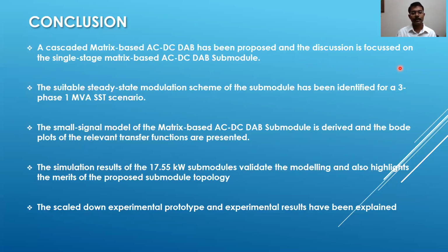And we have also provided the Bode plots of the relevant transfer functions that might be useful for control system design. We have shown the open loop simulation results of the 17.55 kilowatt submodules that validate our proposed modulation scheme, and also it shows the merits of the proposed submodule topology, and it is a holistic discussion of all the possibilities out there.